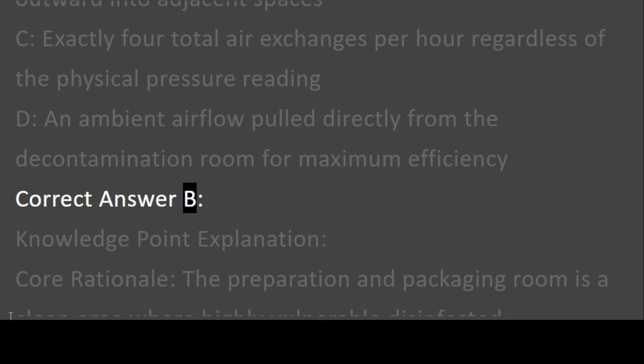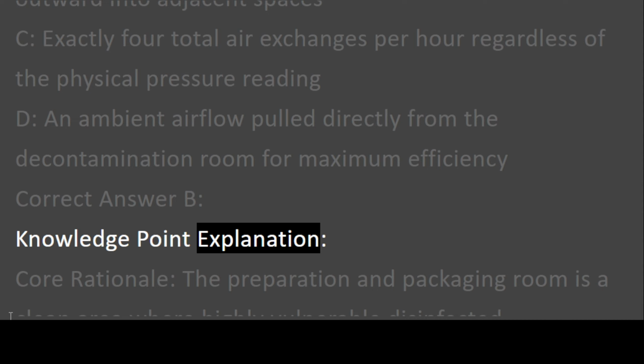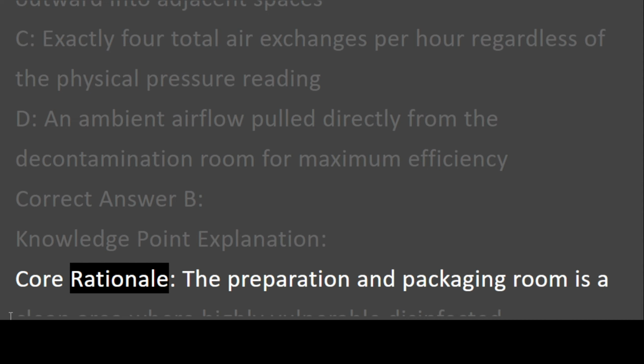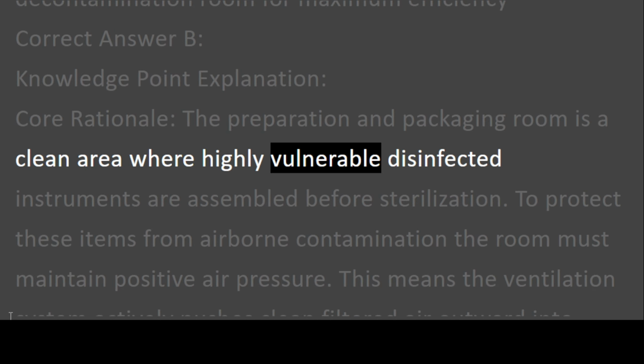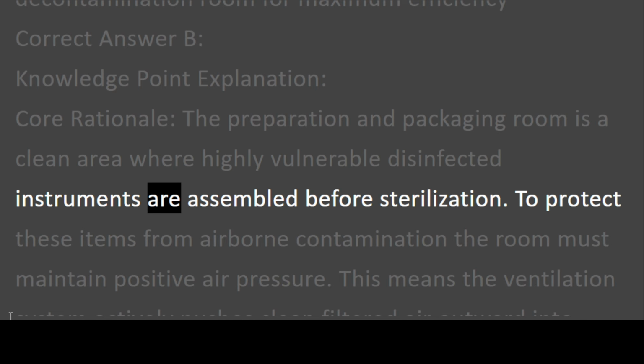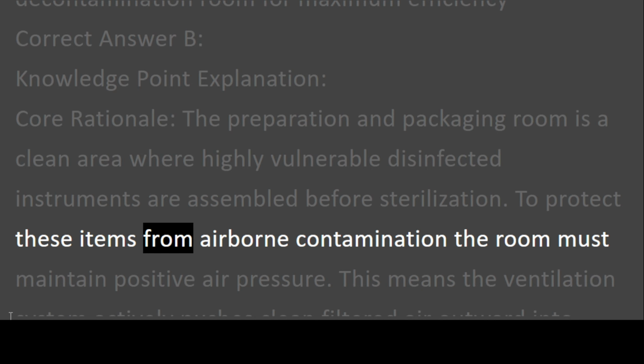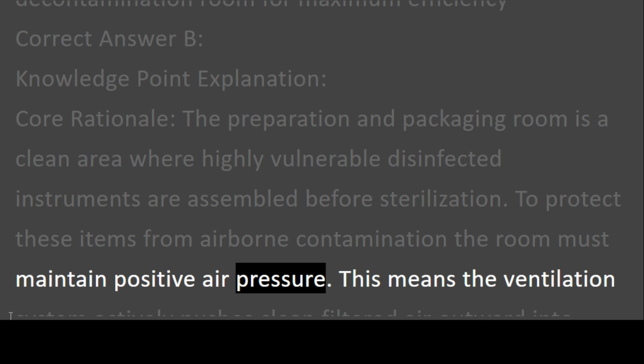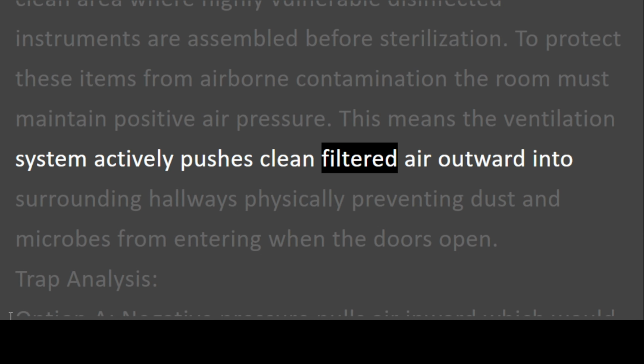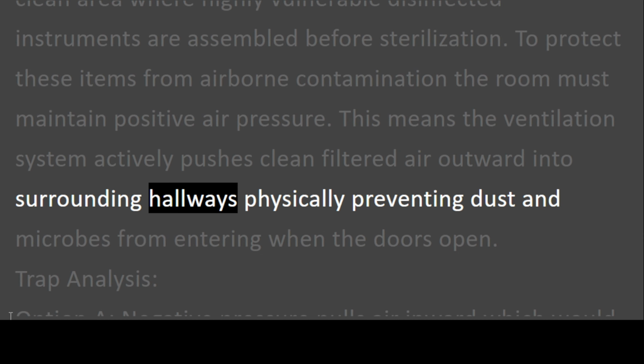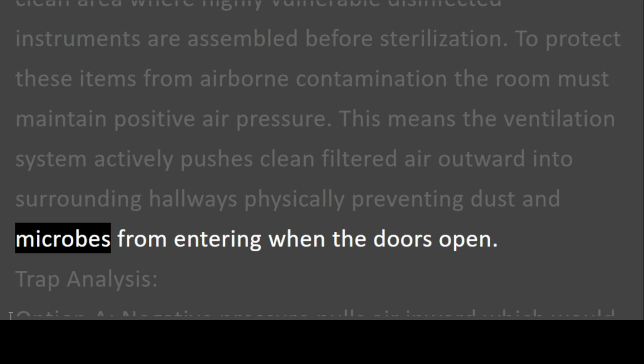Correct answer B. Knowledge point explanation. Core rationale. The preparation and packaging room is a clean area where highly vulnerable disinfected instruments are assembled before sterilization. To protect these items from airborne contamination, the room must maintain positive air pressure. This means the ventilation system actively pushes clean filtered air outward into surrounding hallways, physically preventing dust and microbes from entering when the doors open.